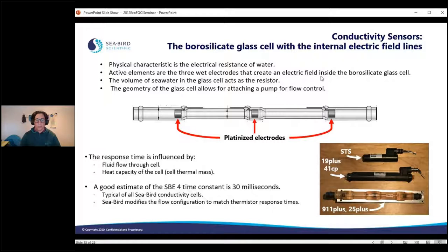So how much water is in those electric field lines. It's really, really simple. There's a lot of things that actually affect this sensor itself. The fluid flow through the cell actually affects that, which is one of the big reasons we use pumped flow. We force water through this using a mechanical pump. By doing this, you can reduce the response time and get a much better response.